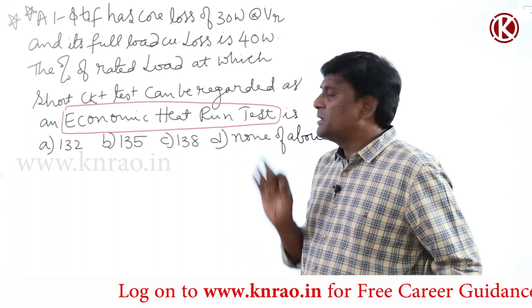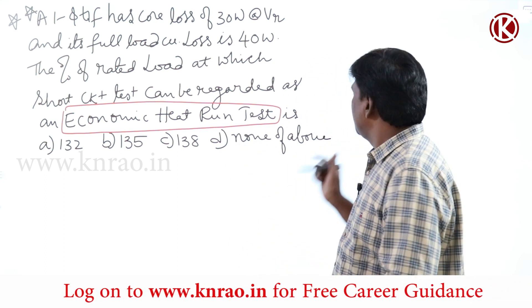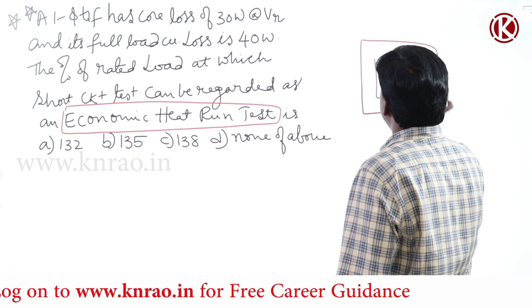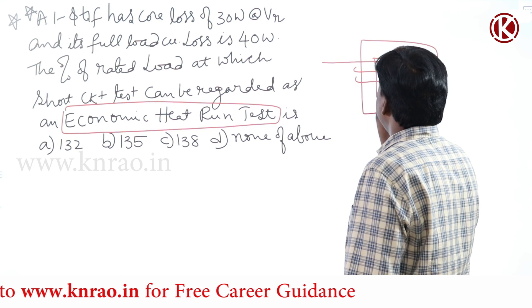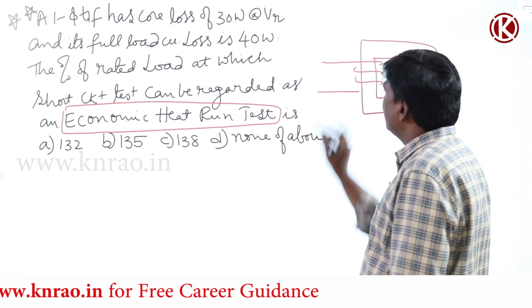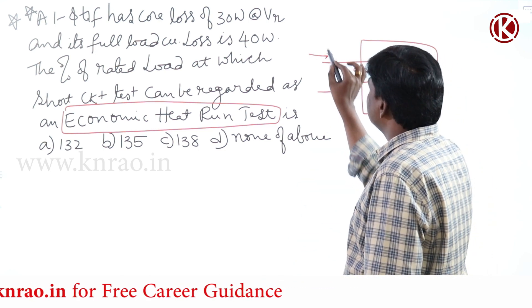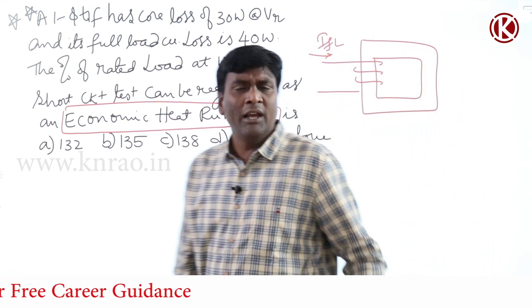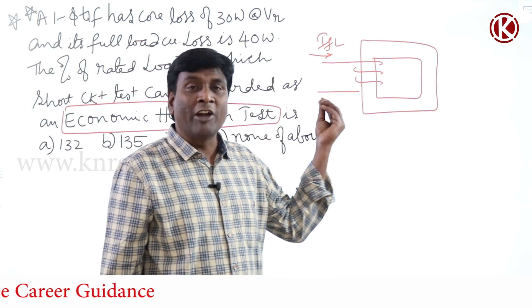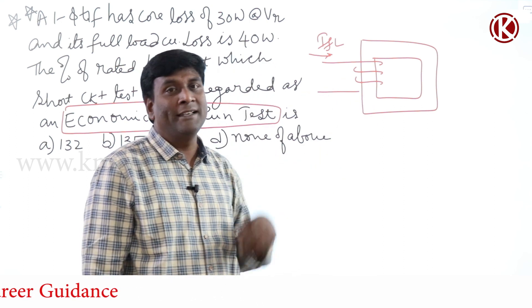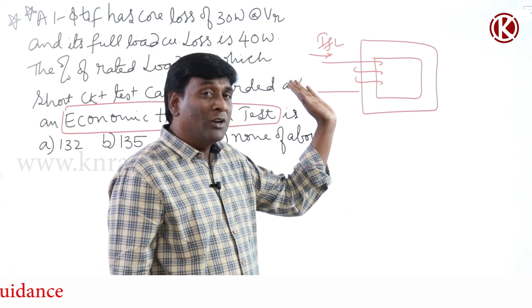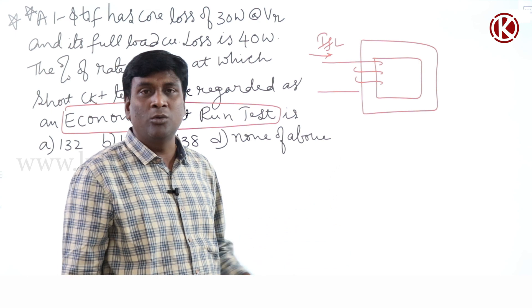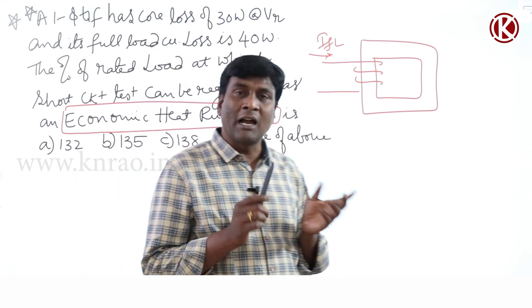What is meant by economic heat run test? Think of a transformer with a winding. If this winding is designed for full load current and I inject full load current, my copper wire volume is going to be fully utilized. But if I inject more than full load current, what will happen? My copper wire will burn.